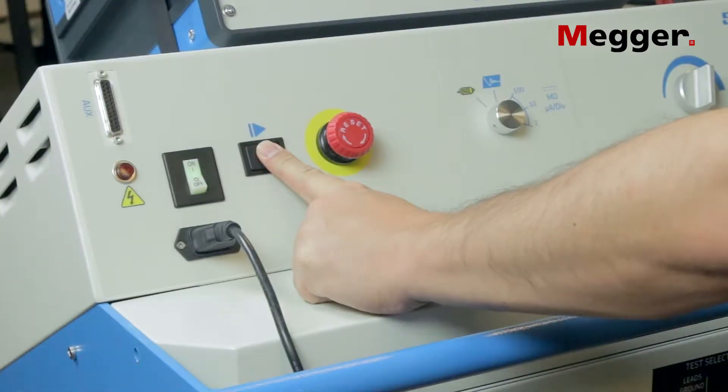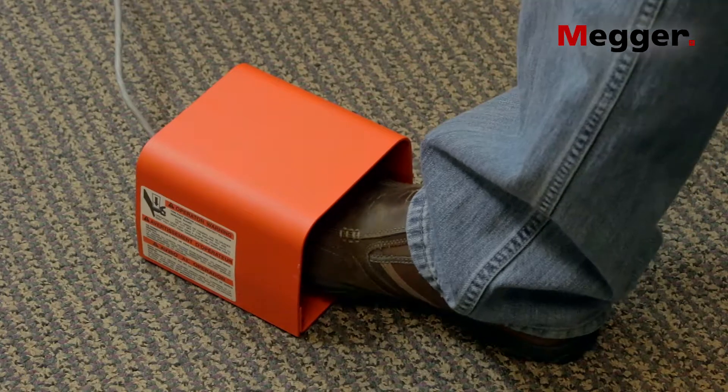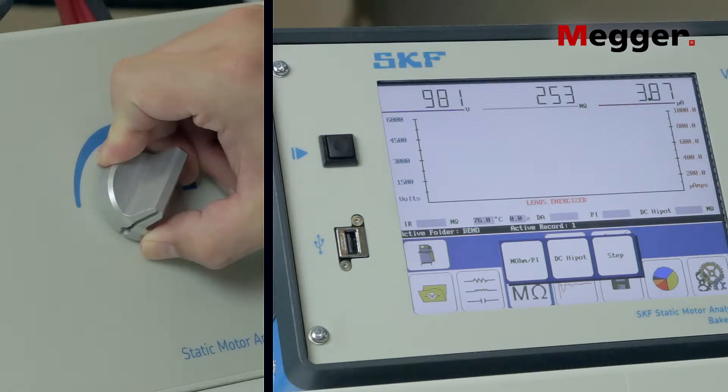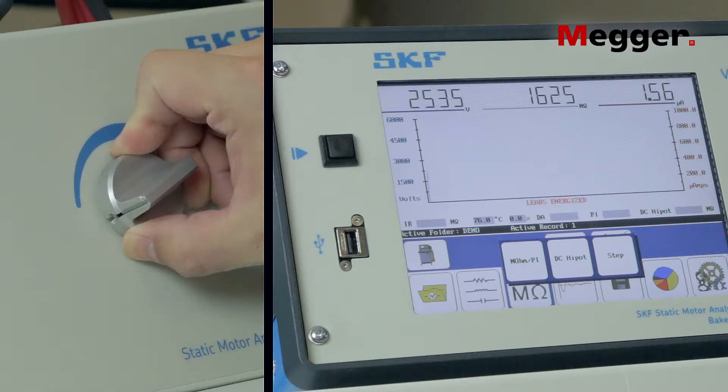Press and hold the push to test button or press and hold the foot switch if you have one. Smoothly turn the voltage control knob to raise the voltage to your first step. In this case, it's 2,500 volts.